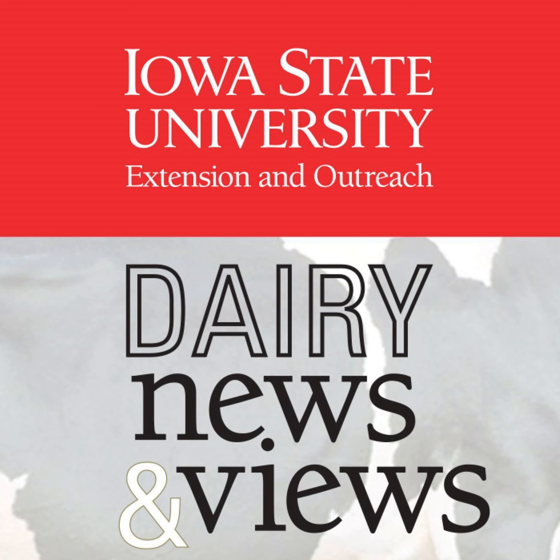The second area I would look at is definitely going to be the holding area. Cows are packed in there, fairly close together. There can be significant heat stress in the holding area. There aren't really any specific recommendations for airspeed in the holding area, but my approach there is the more the merrier. You typically don't have to worry about over ventilating the holding area. Usually a pretty small area, relative to the whole barn. So you can justify having a few extra fans there. So hanging fans or recirculation fans are a pretty common option for holding areas. Some facilities have gone to positive pressure tubes or other type systems there as well.